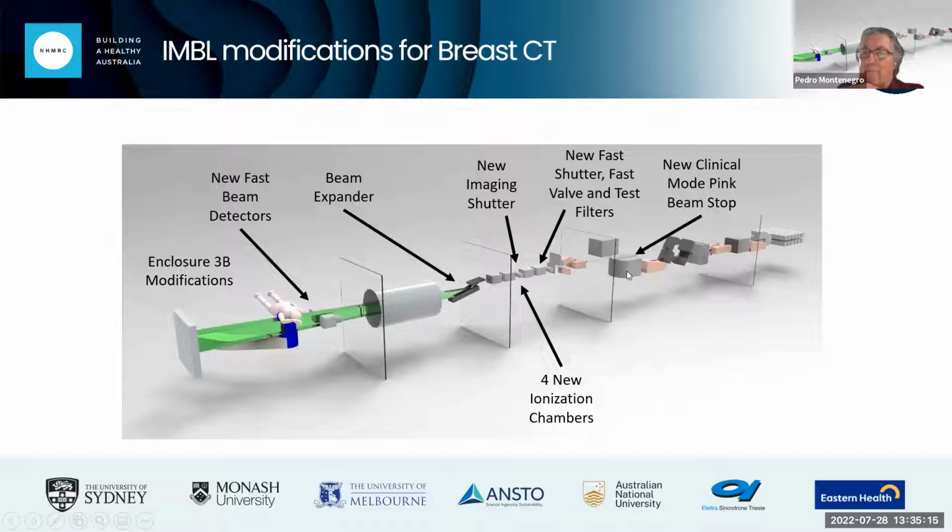And when it is lowered mechanically by hand into position, it is locked with a fortress key, which is the highest level of key system you can purchase. And that key, once it is removed, makes it impossible for the block to move. It basically means that the deadly, and I mean death ray, the pink death ray, cannot go anywhere outside this first enclosure.